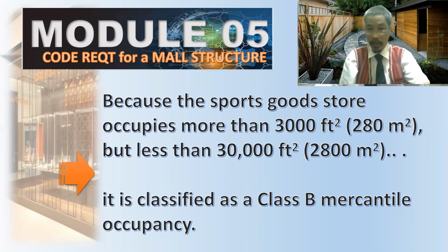So 929 is between 280 and 2,800. Therefore, it is classified as a Class B mercantile occupancy. That is our sub-classification. We are able to confirm.